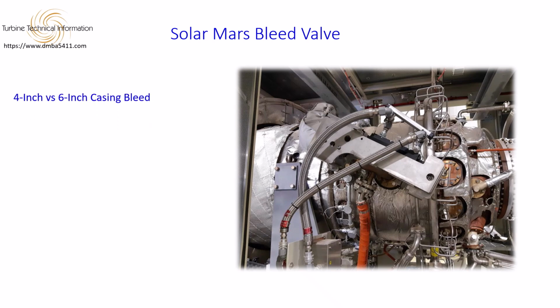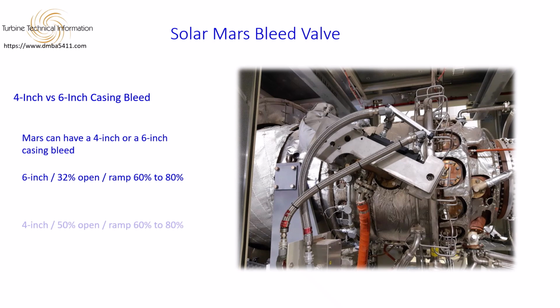4-inch versus 6-inch casing bleed. Now we get into configuration. The Mars can have a 4-inch or a 6-inch casing bleed. That is not a small detail to the control system. With a 6-inch bleed, the valve sits at 32% open below 60% corrected NGP, then ramps closed from 60% to 80%. With a 4-inch bleed, it sits at 50% open, then has the same closing ramp. Why the difference? Because the flow capacity is different. Bigger pipe, flows more air for the same valve position.